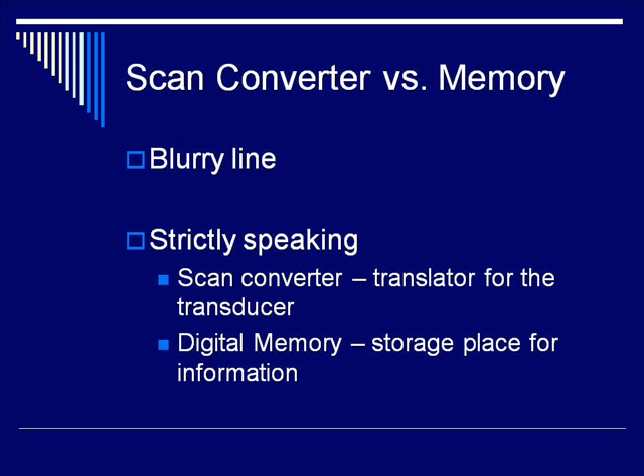The scan converter and digital memory — it's not really easy to describe what the difference between these two are; it's kind of a blurry line. Strictly speaking, digital memory is a storage place for information. The scan converter is technically the translator for the transducer, but in real terms, the scan converter is a computer processor and a certain part of digital memory.